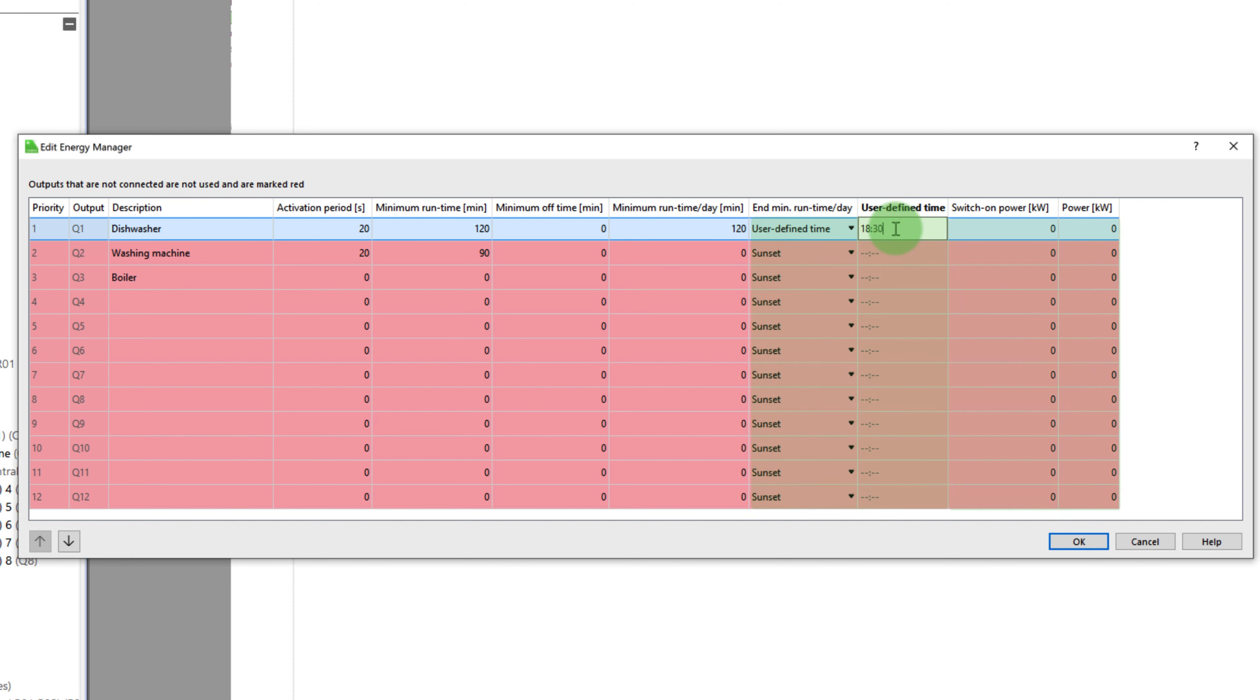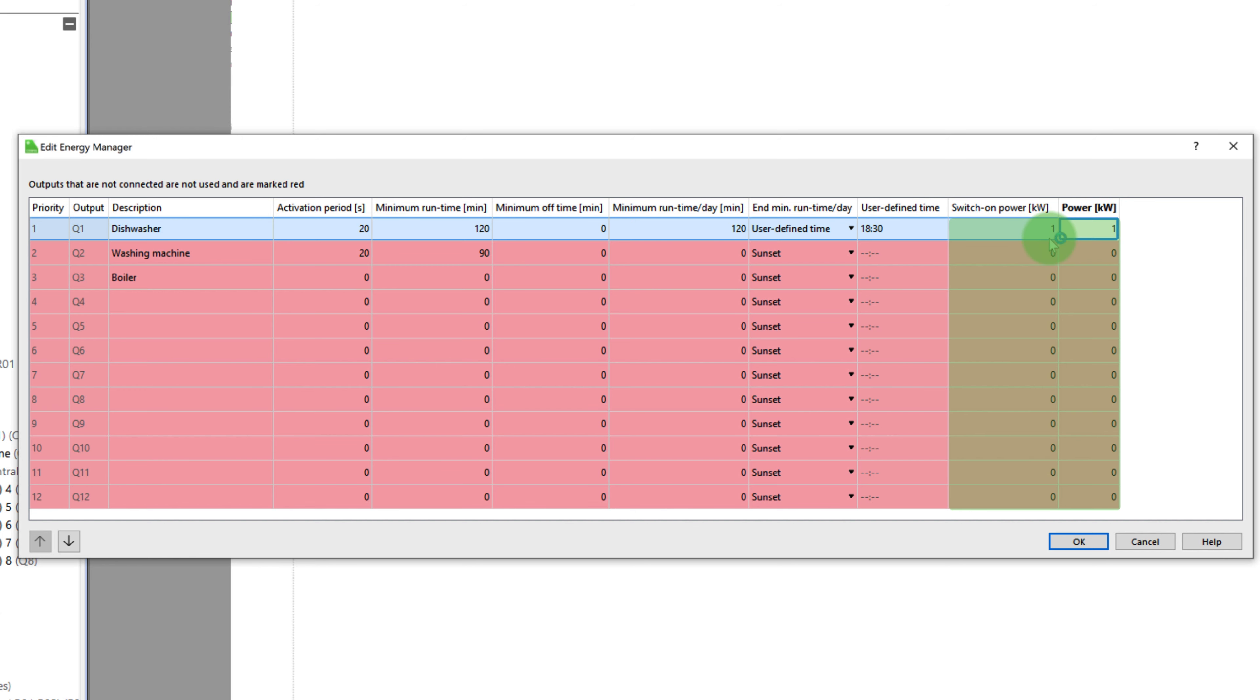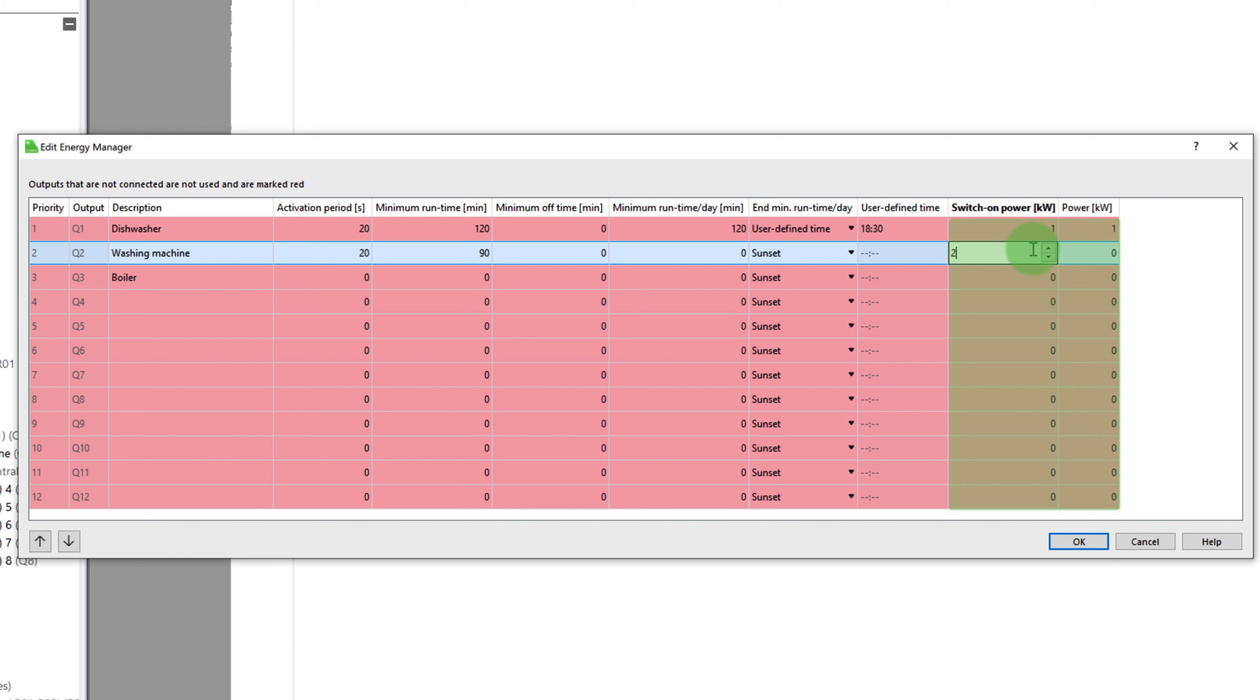If no more surplus energy is available, the function block switches the devices off again. A device that has already reached its minimum runtime is then turned off to give other devices the opportunity to be activated. With the end of minimum runtime per day variable, you can define the time by which the minimum runtime per day must be reached.